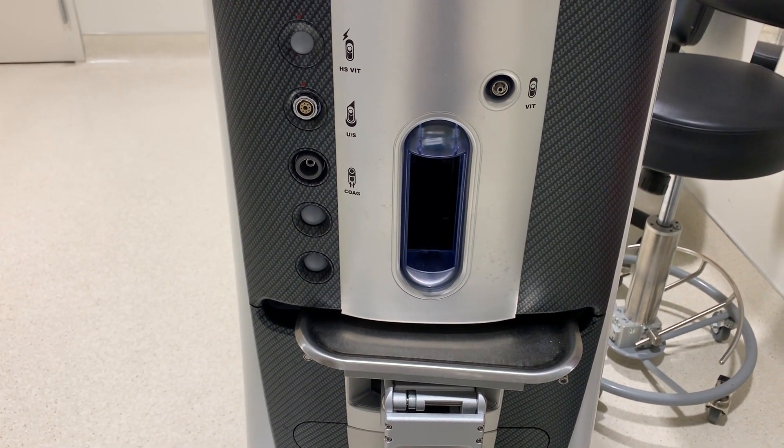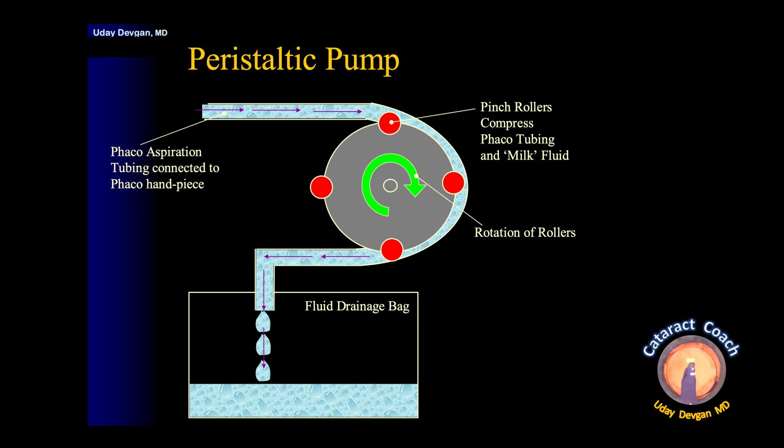So these two pumps are very different. For a peristaltic pump, on the flexible tubing there are pinch rollers that compress and milk the fluid along. This then drains into a fluid drainage bag, not a rigid cassette. The peristaltic pump is probably the most common type used in most phaco machines.